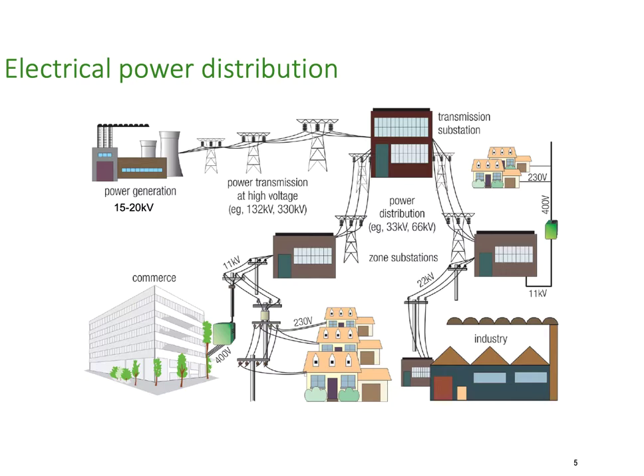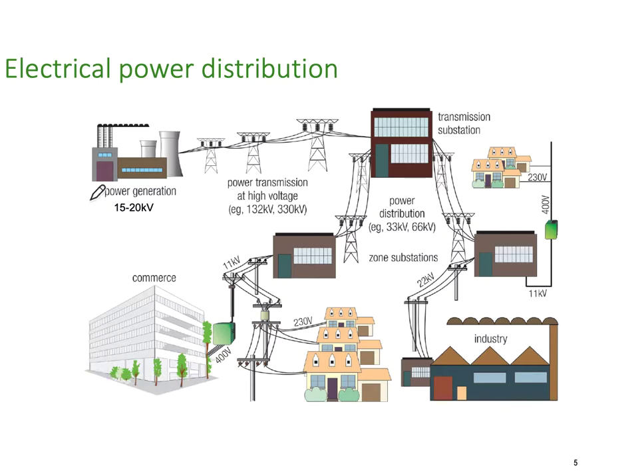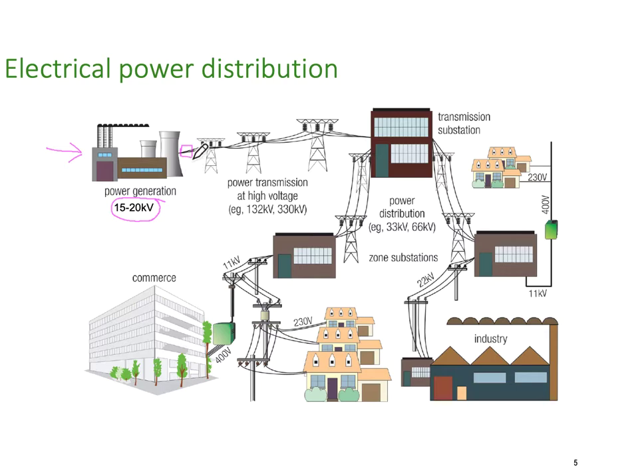Let's have a close look at the electric power distribution diagram. We're going to start over here with generators. Generators could be coal-fired steam generators, solar, hydro, or wind — there are lots of ways to generate electricity. Typically, those generating plants generate at about 15,000 to 20,000 volts. Then as they come out of the generation plant, they have a step-up transformer, and we typically step it up to 132 kV or quite often 330 kV.